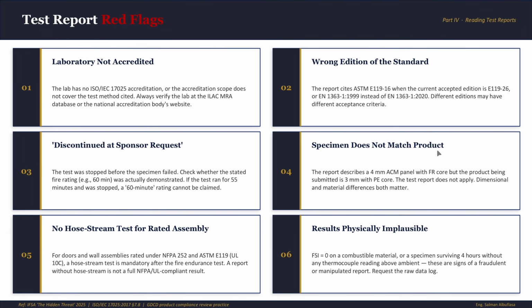And then, specimen does not match the product. Different core material, different thickness, different surface coating, different hardware. If the specimen description does not precisely match what is being submitted, the report does not cover it. No hose stream tests for rated assemblies. For doors, wall assemblies, and anything under NFPA 252 and ASTM E119 or UL 10C, a hose stream test is mandatory after the endurance test. So a report without them when it was required means the test was not complete or something is wrong. There's always an exception, but the exception should always come from the entity that's issuing the standard and not from the lab itself. They cannot exclude, they cannot change anything about the test standard.